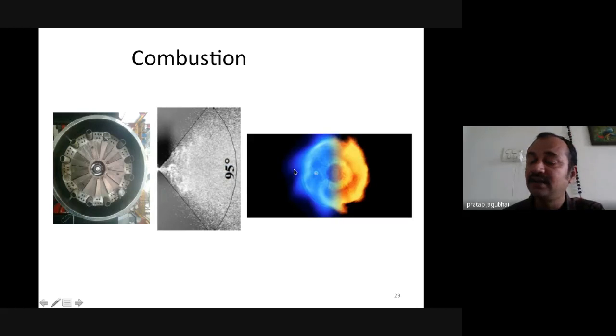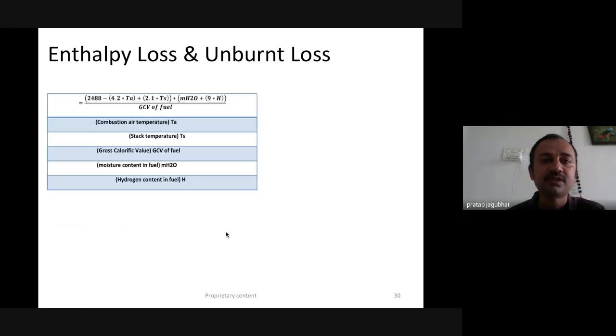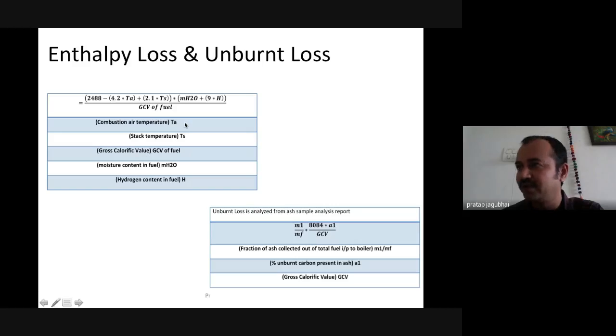And the third important part is providing turbulence. That means providing secondary air or tertiary air in such a way that we can have a swirling flame, and a swirling flame gives a better combustion rate and better coverage across the periphery, and will give better heat. This turbulence is even more important in the case of suspension of the fuel particle to burn like a vapor. That's why even solid fuel burns like a vapor, and that is called fluidization in the case of solid fuel. So these 3 T's are very important to maintain the combustion rate and to control the combustion. Another loss is the moisture loss or enthalpy loss, which we can't do much about, because the moisture available within the ambient air or within the fuel is inherent.